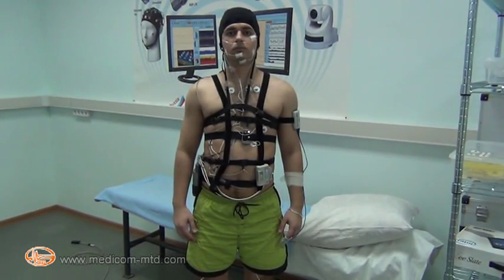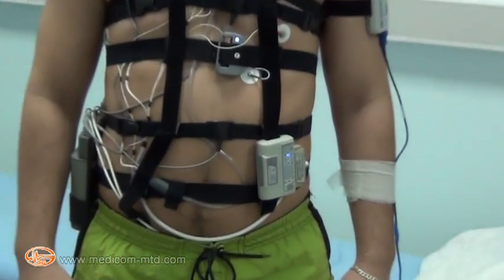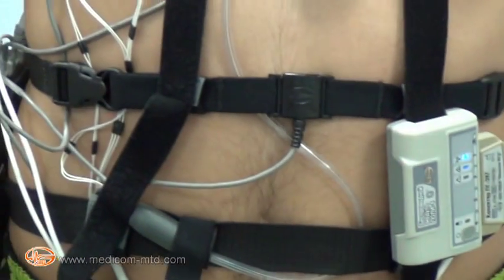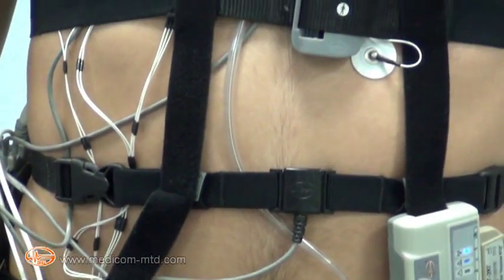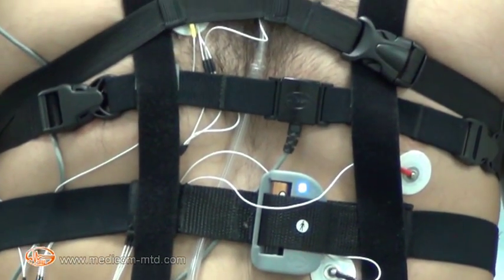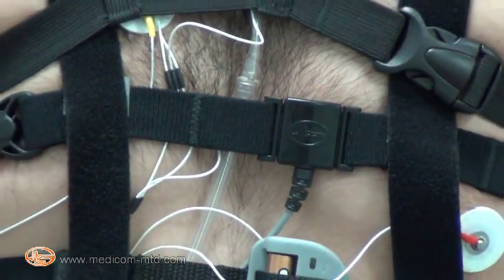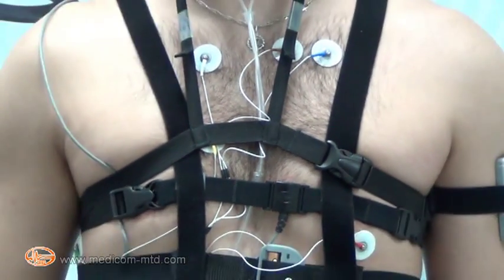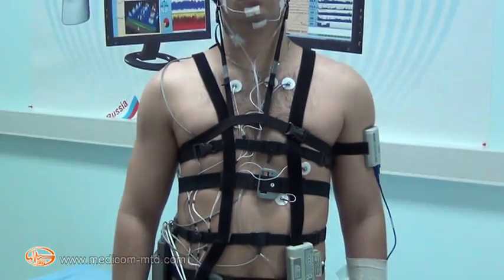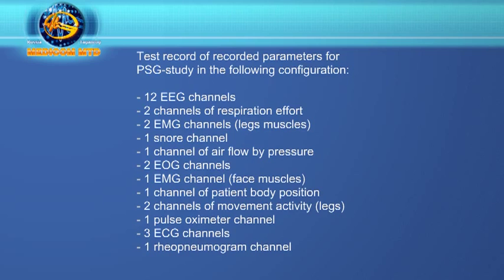General view of the system with wireless module PG-ECG: the module cooperates with ABP via wireless Bluetooth channel and supplements the system with 4 channels for recording respiration parameters — rheogram (1 channel) and ECG by 3 derivations. There are connector slots for wires with touch-proof connectors, color marks for ECG leads identification, and places for electrode attachment.